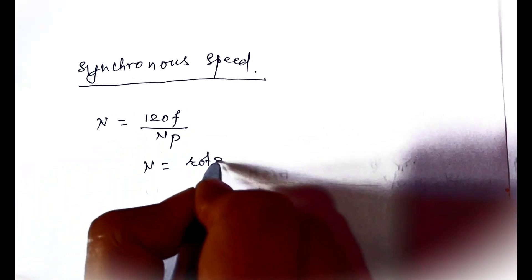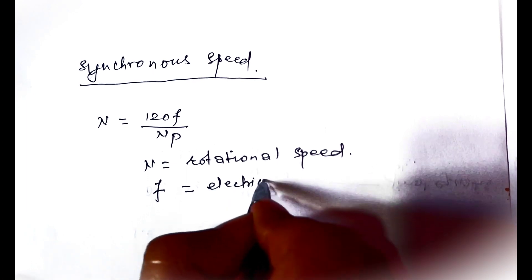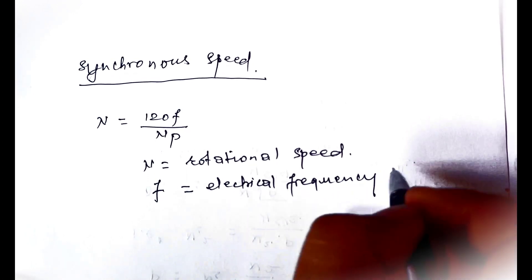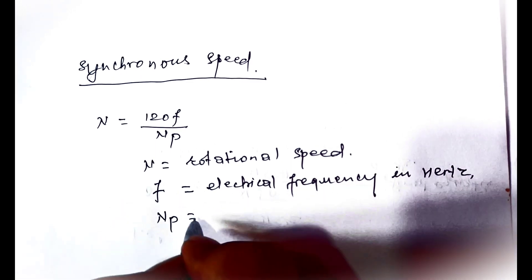Now let's talk about synchronous speed. If the turbine is directly connected to a generator, the turbine speed must be the synchronous speed. The following equation must be satisfied: N equals 120·f / Np, where N equals rotational speed, f equals electrical frequency in hertz, and Np equals number of generator poles.